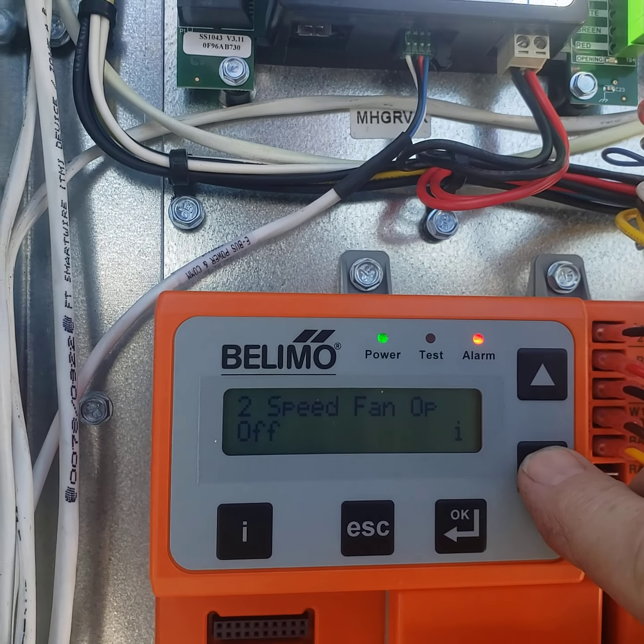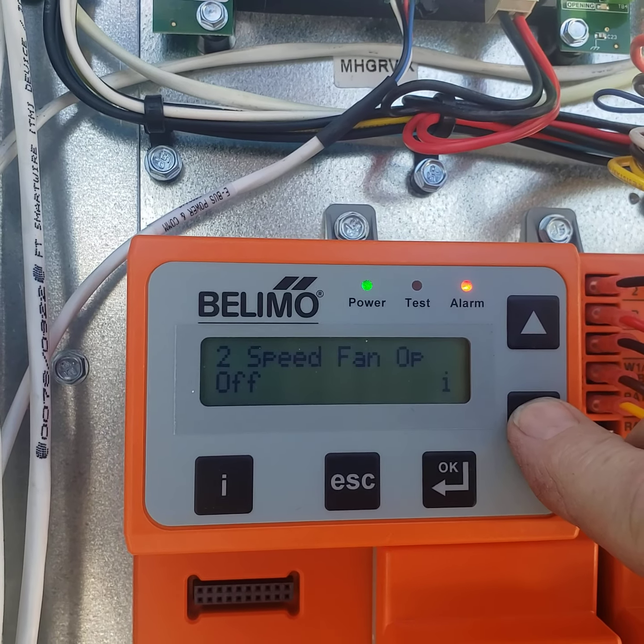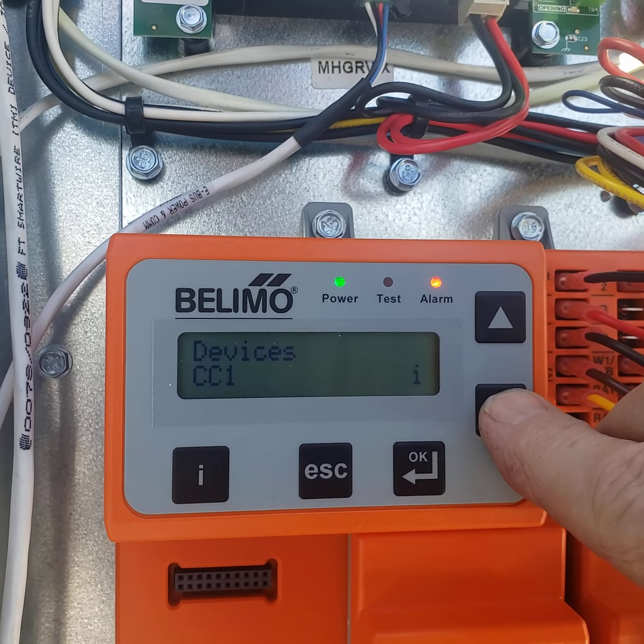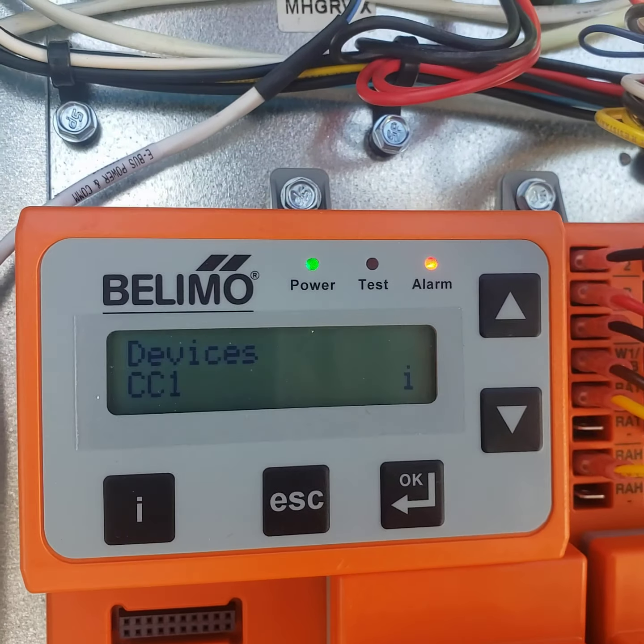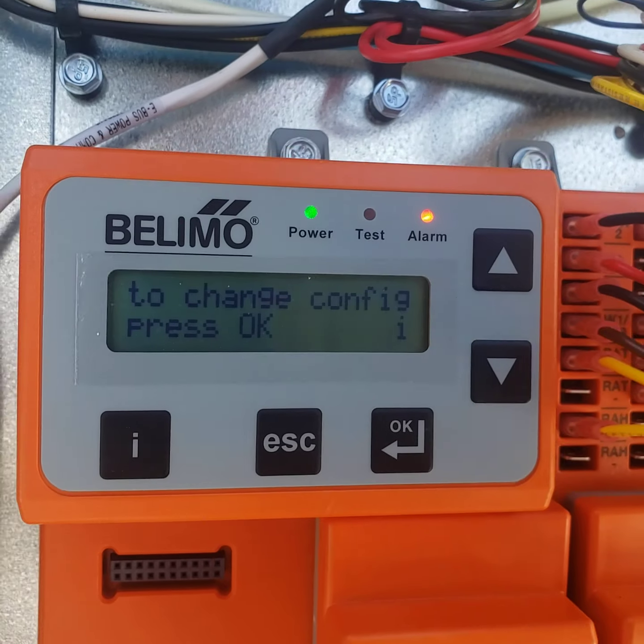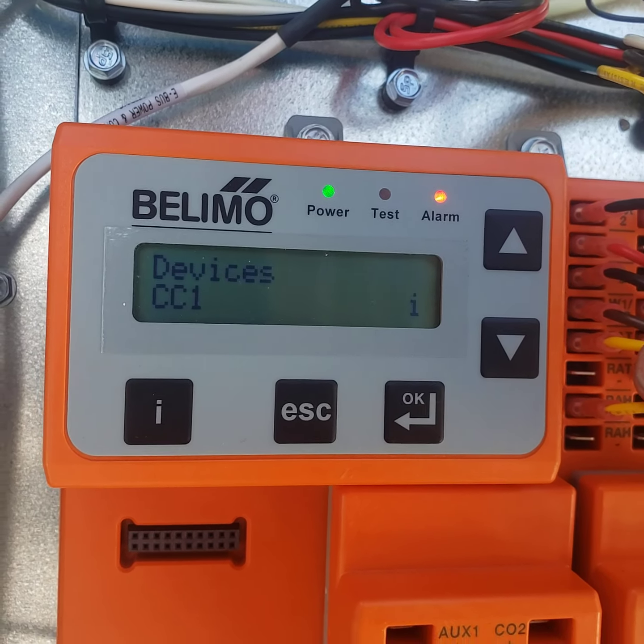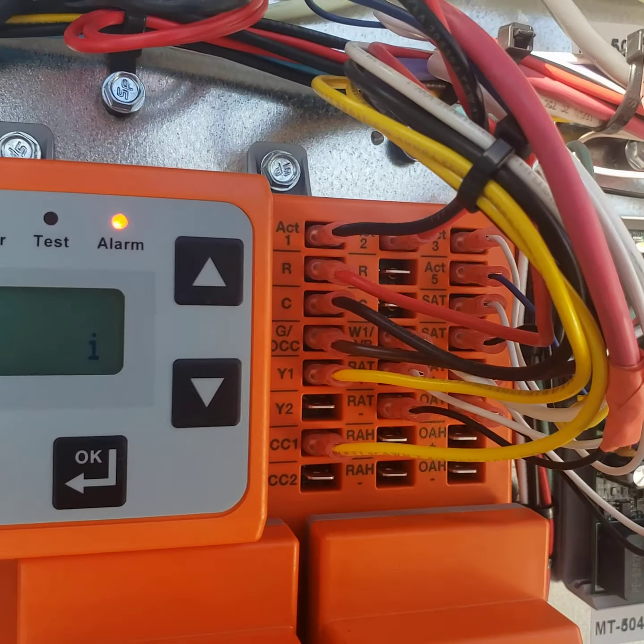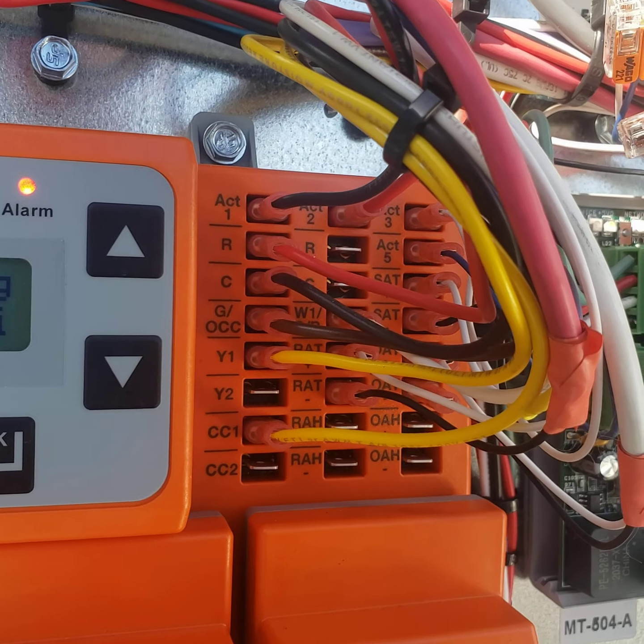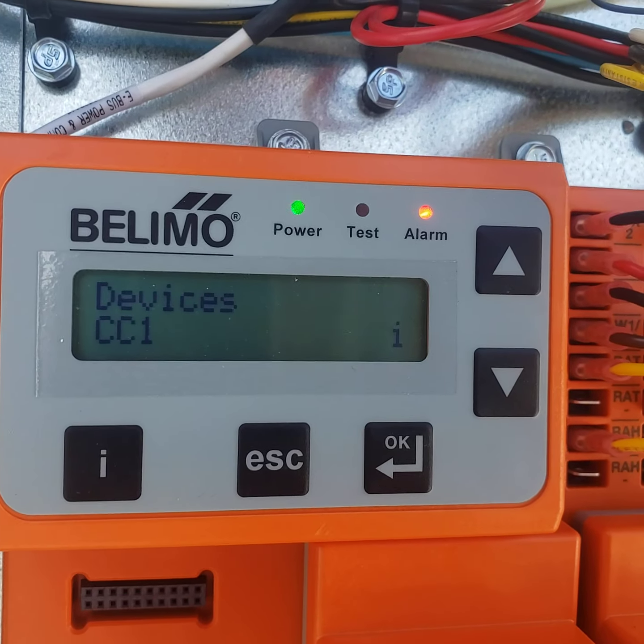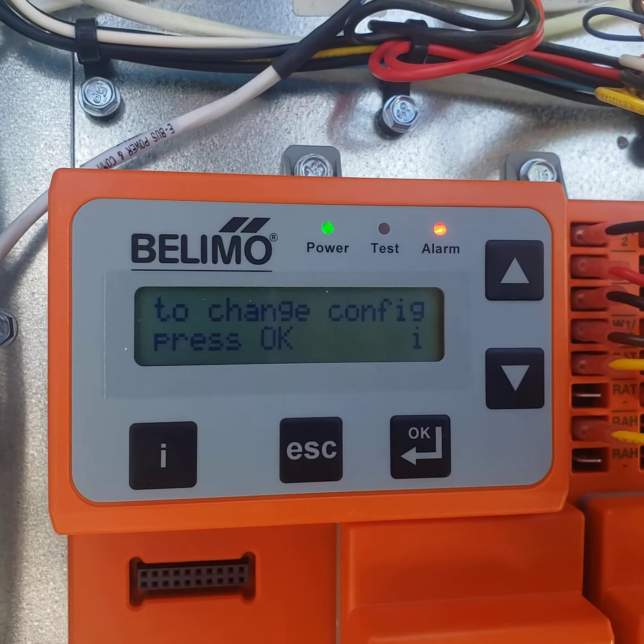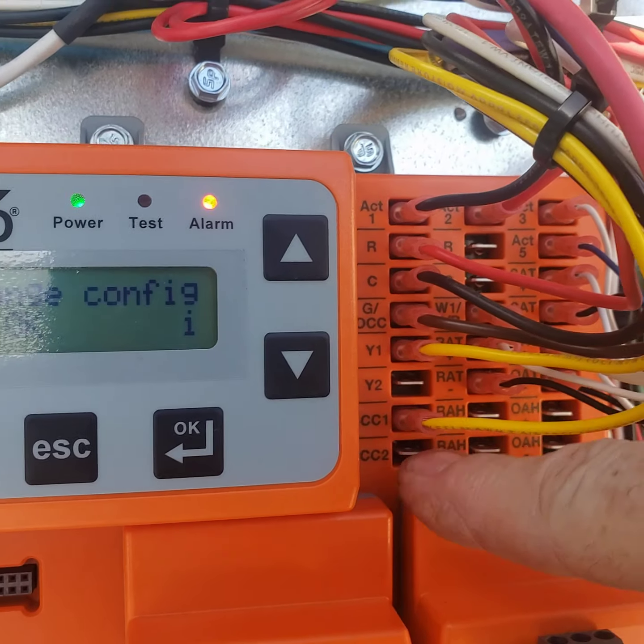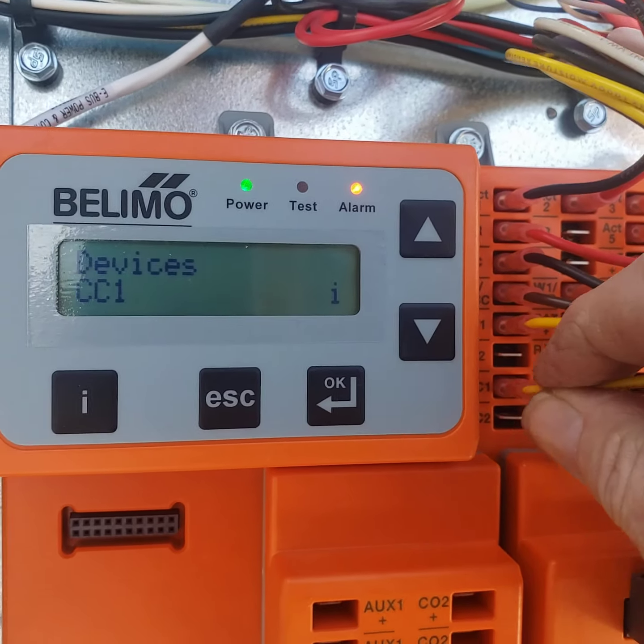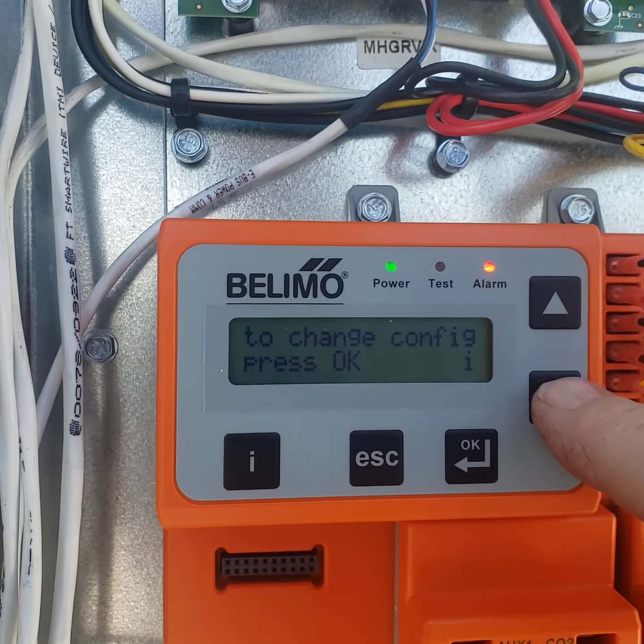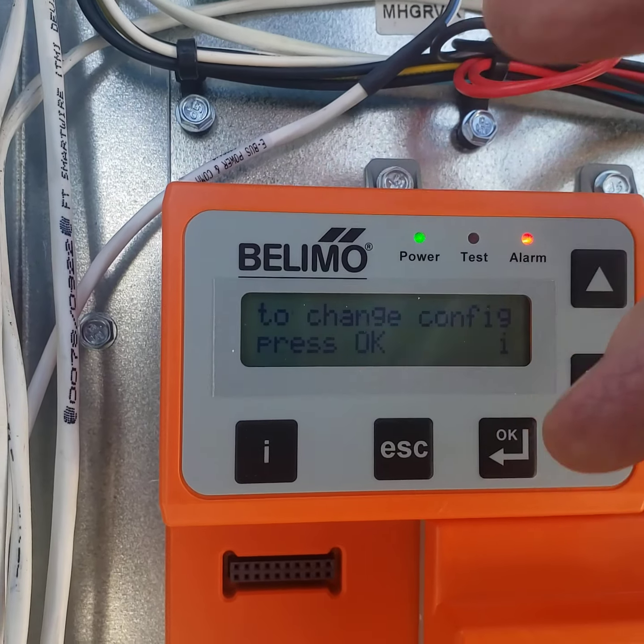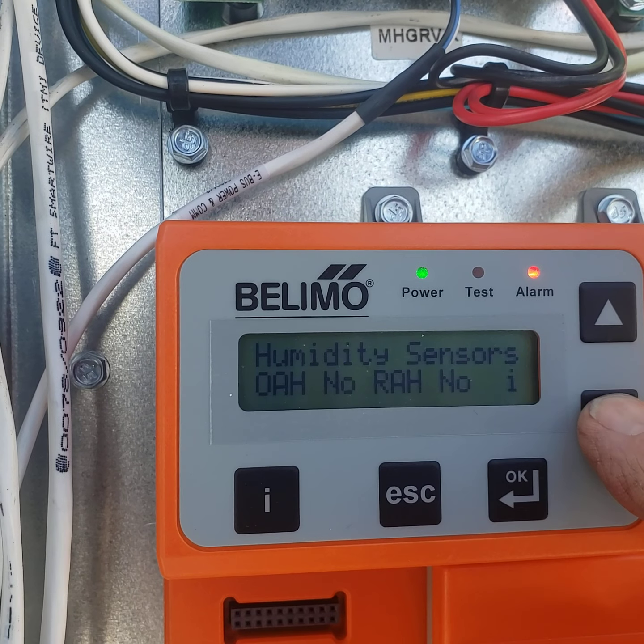Moving right along. 2-speed fan operation. We don't have a 2-speed fan. We don't have a heat pump here. Devices. It asks you how many devices you have. Normally it can auto configure. It senses the devices that are plugged into it and says, oh, we have something here, we have something there, and it'll list them here. In this case, we've got CC1. We do not have a CC2. This is compressor contactor, by the way, compressor contactor 1 and 2. We can manually make changes to that if we wish.